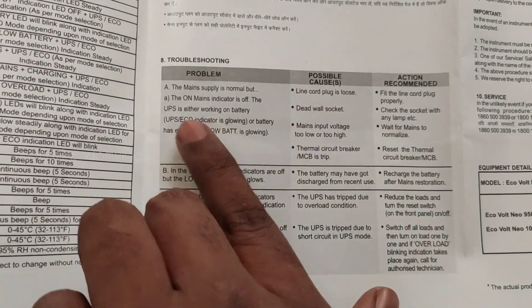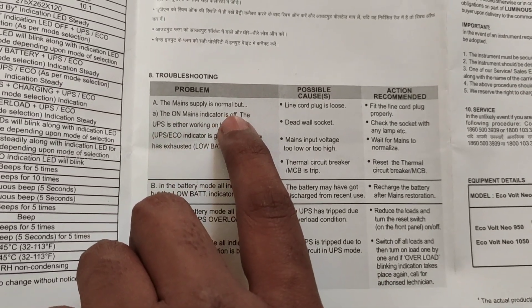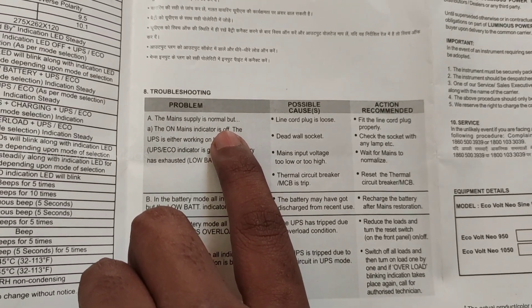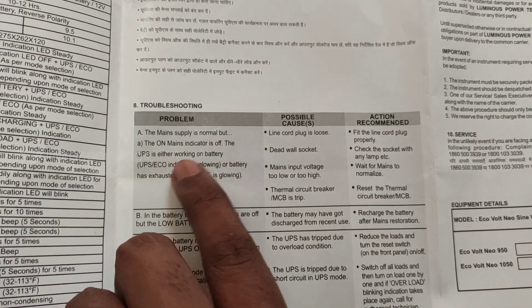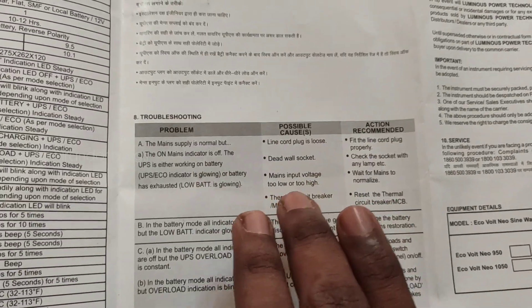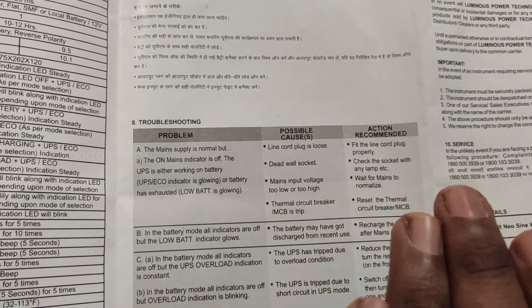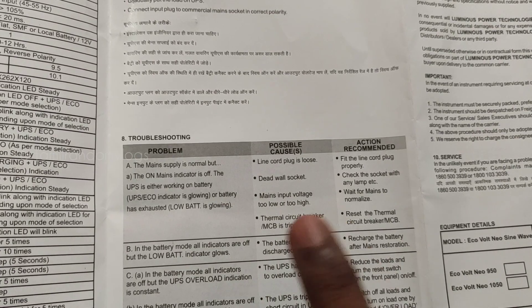The main supply is normal but the main indicator is OFF. That is, the main supply indicator is OFF. But we have inverter supply — the UPS is working on battery. The UPS/ECO indicator is glowing. The main indicator is OFF; there is current but the main indicator is not active in the inverter.